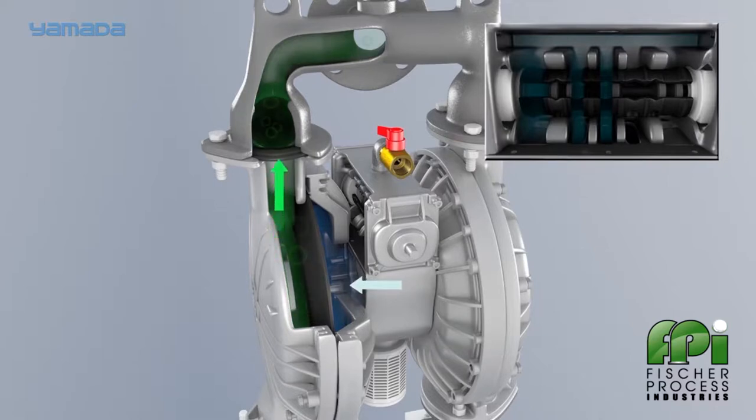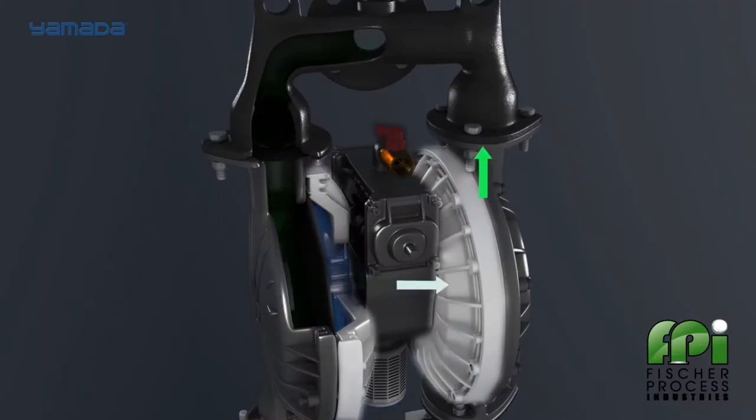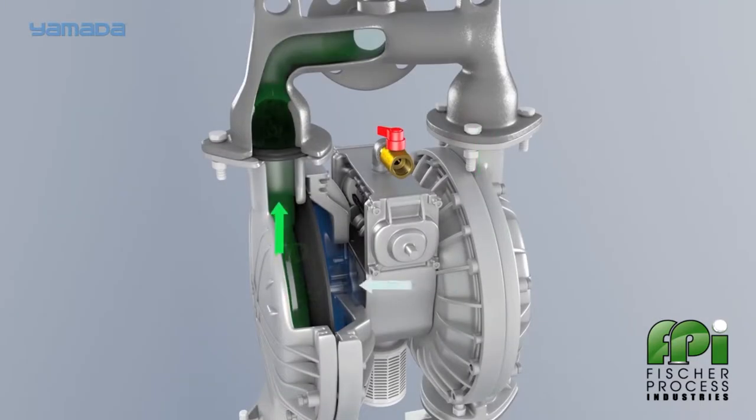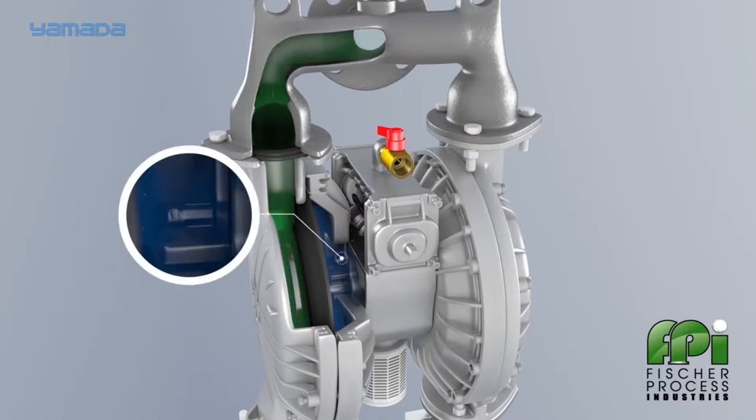As the air enters the chamber, it forces the diaphragm outward. This outward momentum forces liquid out of the discharge ball valve and loads the opposite inlet ball valve. As the diaphragm travels outward, the connected diaphragm on the opposite side is pulling the diaphragm inward. When it travels a full stroke, it will contact the pilot valve, depressing it and breaking the seal to open an exhaust port.